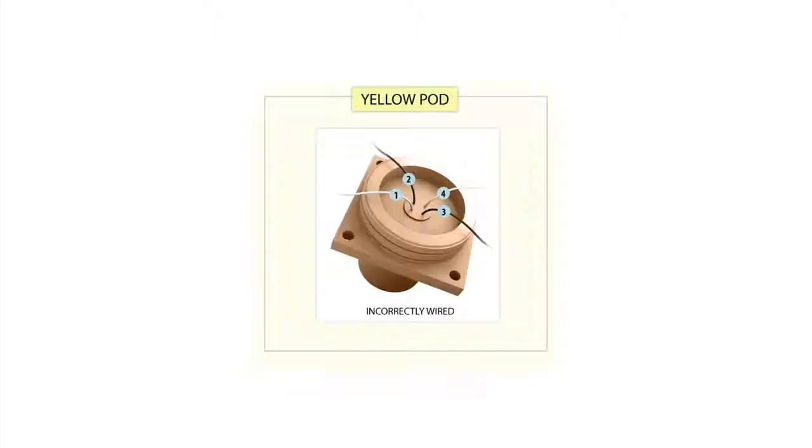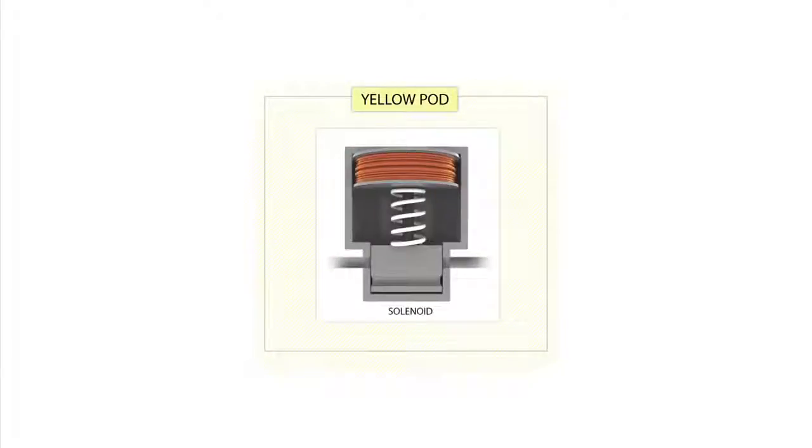And within the redundant Yellow Pod, the solenoid for the blind shear ram had been miswired. The solenoid valves were controlled by two coils of electrical wire. These two coils were designed to work in concert, generating a magnetic field strong enough to operate the valve. But within the miswired solenoid valve, the two coils actually opposed each other, leaving the valve paralyzed.